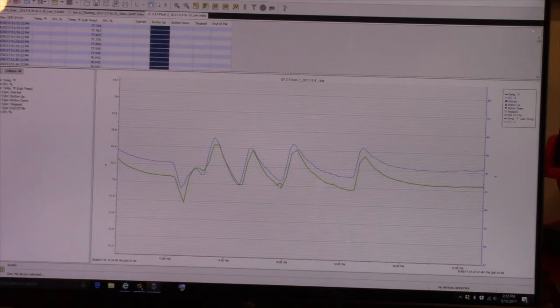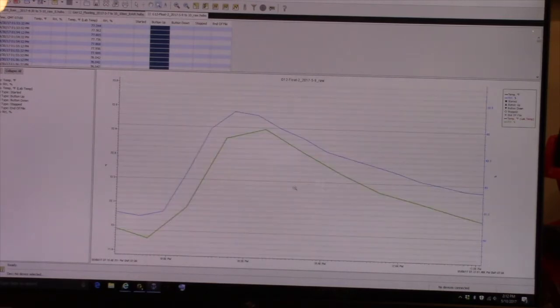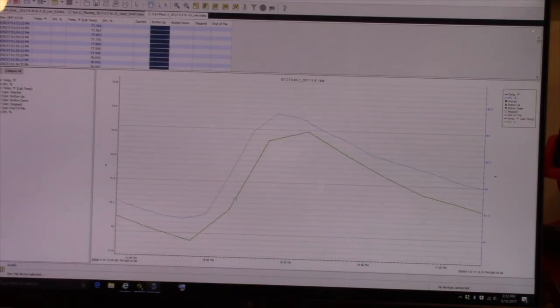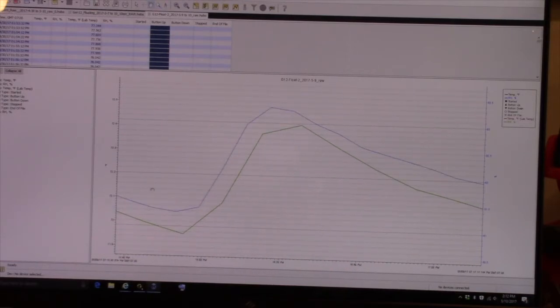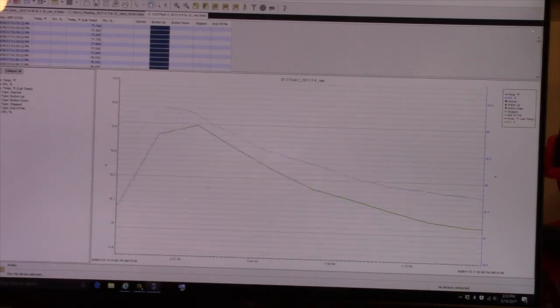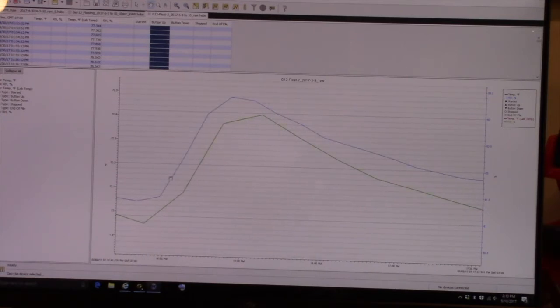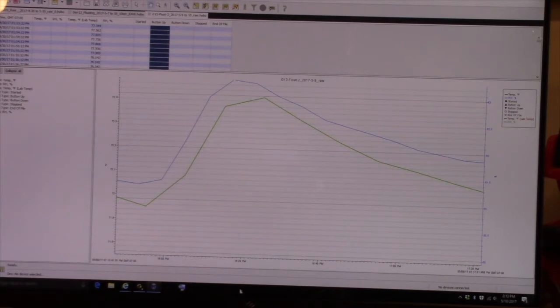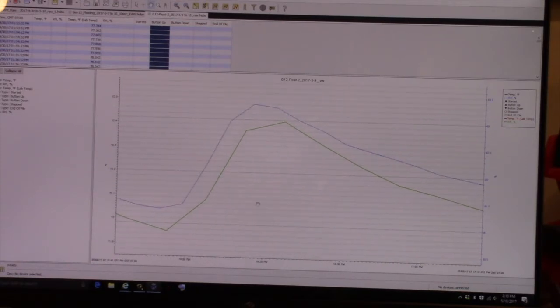Okay, so you can see a lot happens within this span of 1 minute, and you simply aren't going to see this by taking an instrument, and this would be a test instrument, and telling it to take a sample here and then a sample here, because when you've done that, you've completely blown this change out. And if this change happened to be really pronounced, say 10 or 15 or 30 RH, you can essentially chop it out with this lower resolution type instrument.